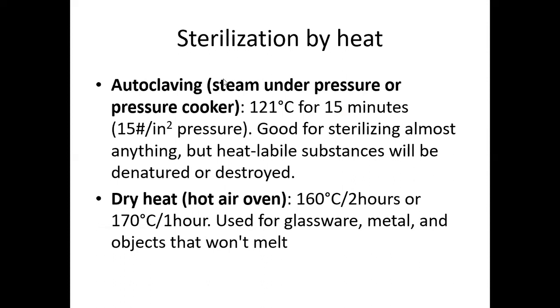Also, we have such a method as autoclaving, and in autoclaving we use steam under pressure. The temperature is about 121 degrees, the pressure is about 15 pounds per square inch, and the time of sterilization is not less than 15 minutes.